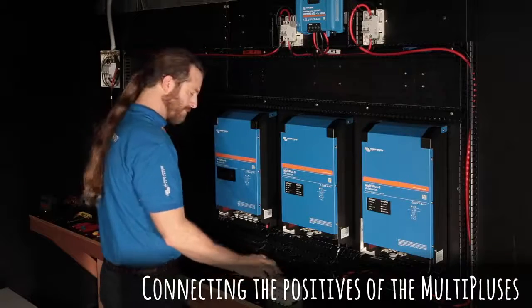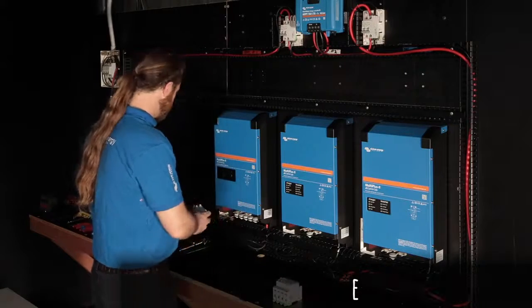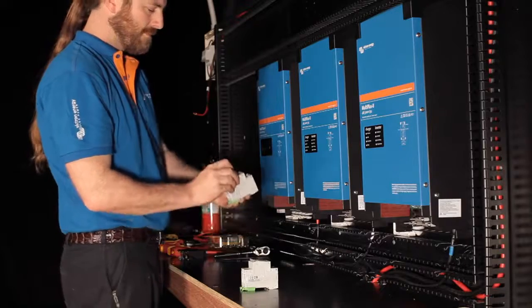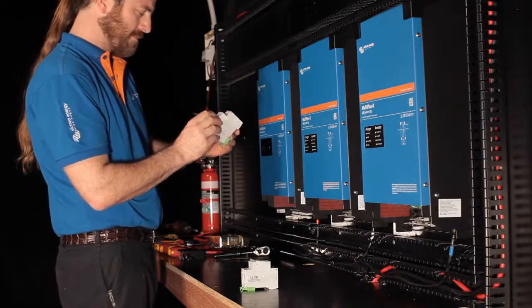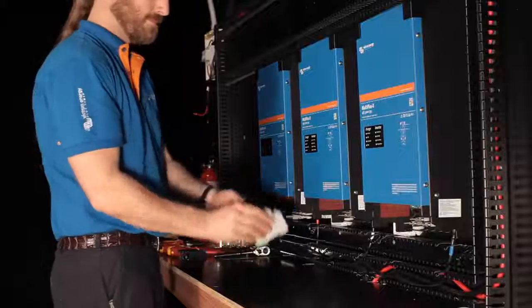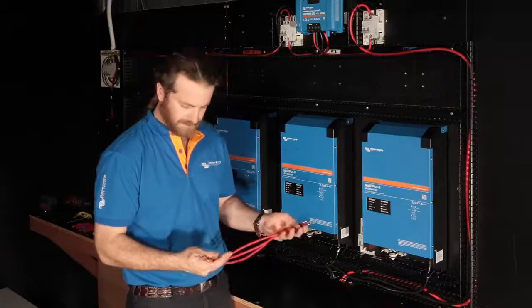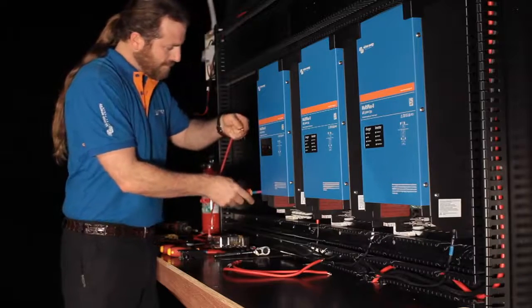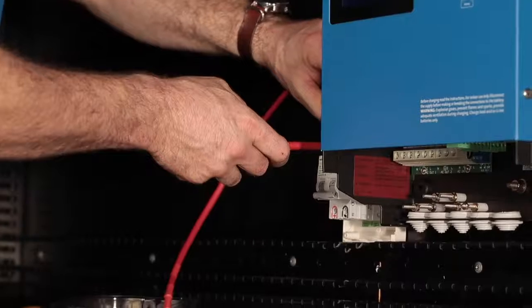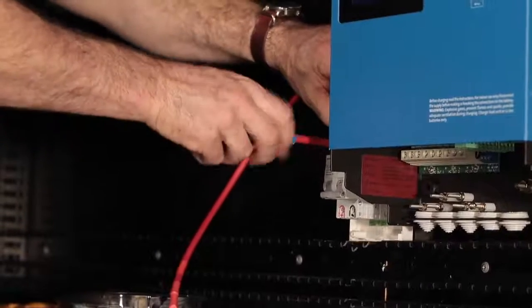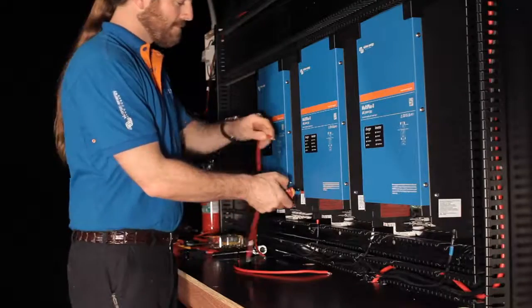Once you've got the negative battery cables in place, you can then connect the positive battery cables. In this case, we can isolate these through a switch. We'll be using a double pole DC isolator, but only using the positive pole of it. If you can find a single pole DC rated isolator, then you can use that too in this case. This one's current rated to protect the cables.